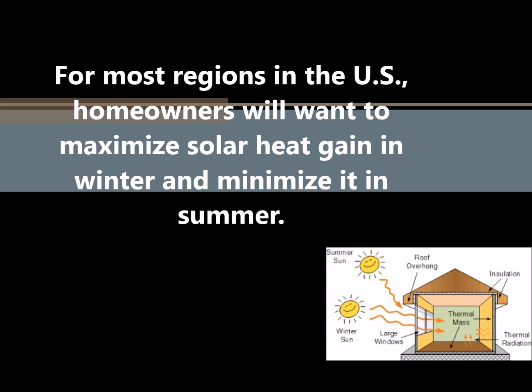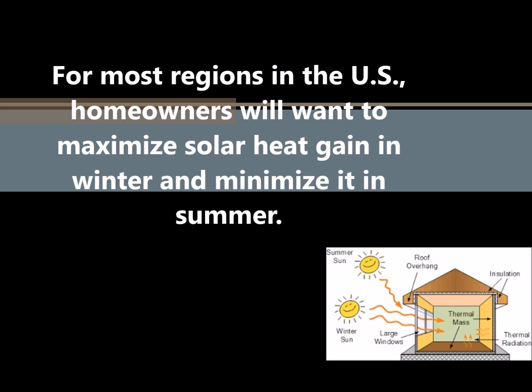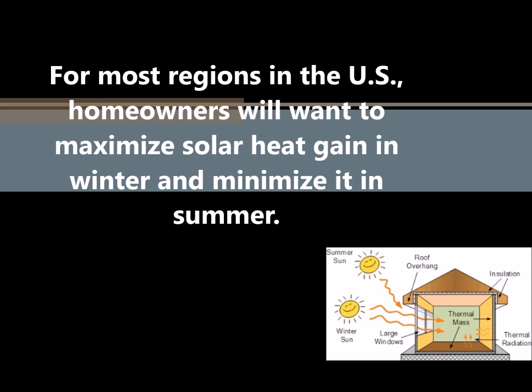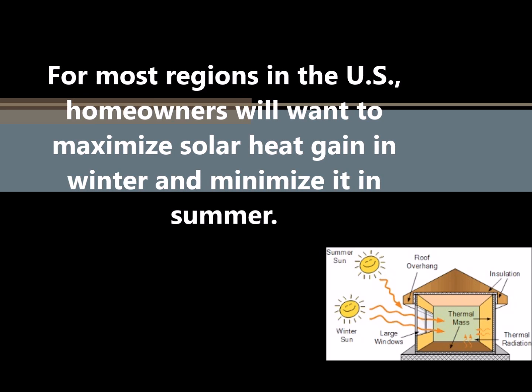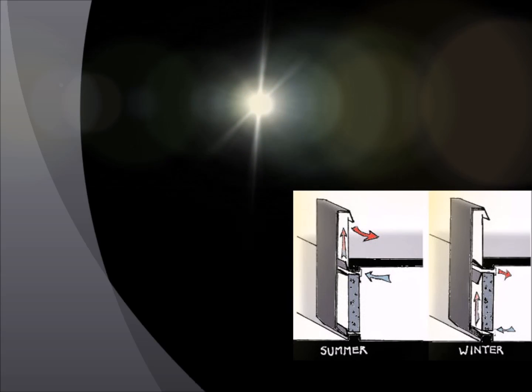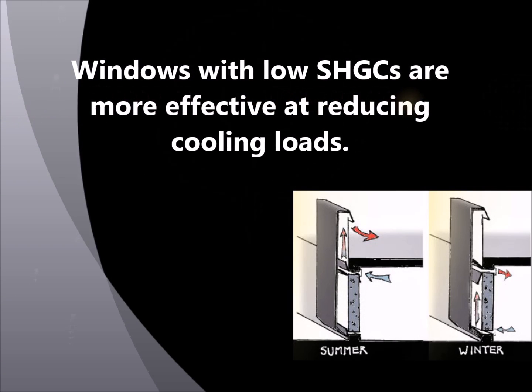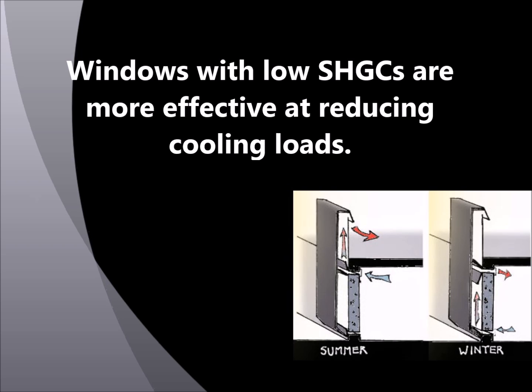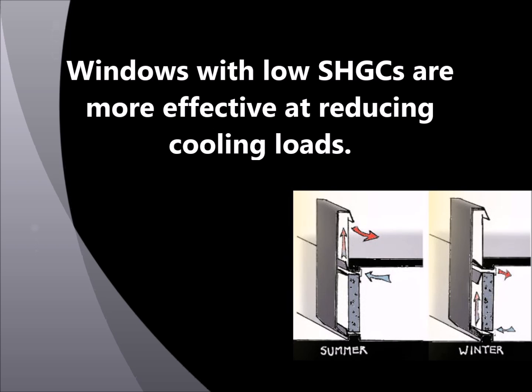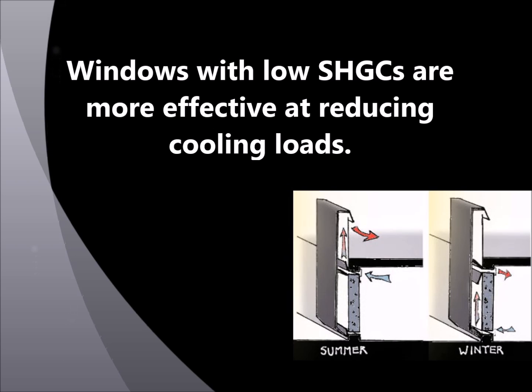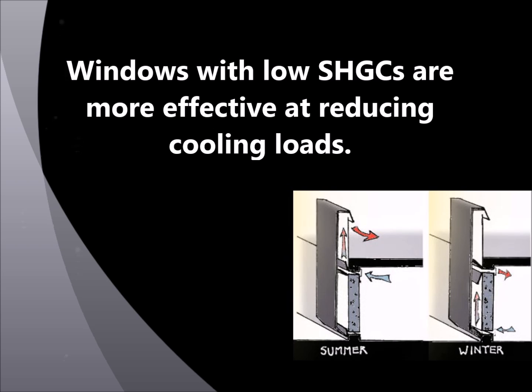Next we look at cooling dominated climates. In cooling climates, particularly effective strategies include preferential use of north facing windows and generously shaded south facing windows. Windows with low SHGCs are more effective at reducing cooling loads. The following types of glazing help to reduce solar heat gain and lower a window's SHGC: tinted windows, reflective, low-E, and spectrally selective. Most of these glazing types, except for spectrally selective, also help to lower a window's VT.